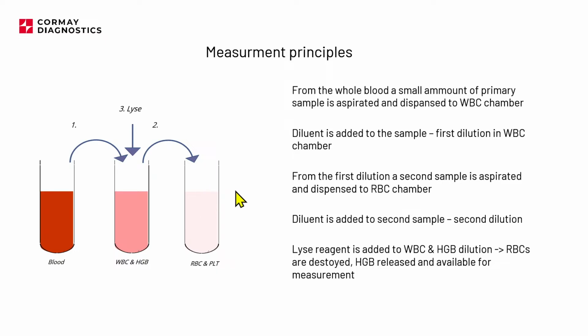For the RBC PLT, we're only adding a diluent, but please keep in mind that this is a series of dilutions. We diluted the sample twice, and actually the color can suggest something to you, right? Here is 20 microliters in a big volume of diluent, and later we are taking a little bit of this and going here, so you can see that the color is only barely present here, right? In real life, in the analyzer, you will not see any color in the RBC PLT chamber, because the number of cells in this dilution is so low that it allows the analyzer to make measurements, but the color change is barely visible. I will say you will not see any color change, so you will think that there is only diluent in the chamber, but in reality it's different. We have the RBC and PLT in this chamber.